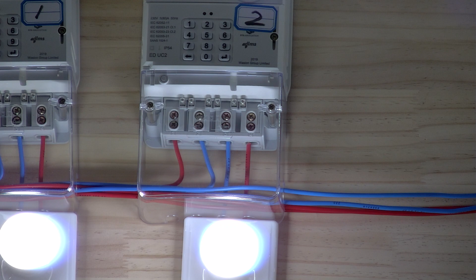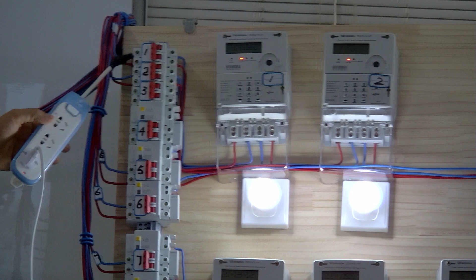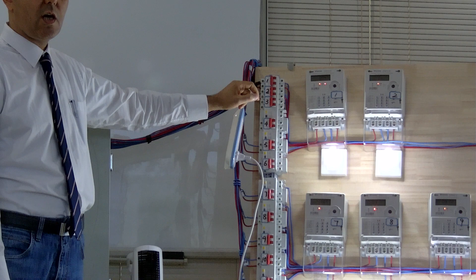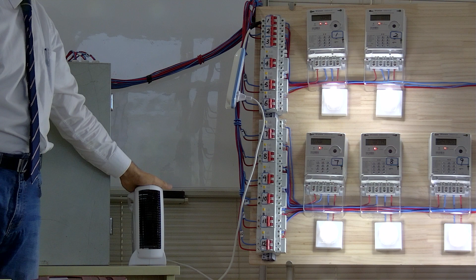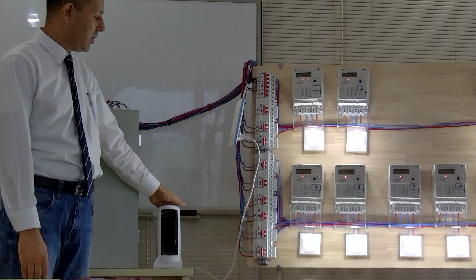Meter number one belongs to a bad customer who is going to tamper with or bypass the meter. As you can see here, we connected one big load to the incoming side of meter number one, connected to the utility grid. This load is a heater with high consumption, and it represents a tamper for meter number one. Whenever it's the right time, I'll turn on this heater, and you'll see how we detect this tampering and how we disconnect the load.